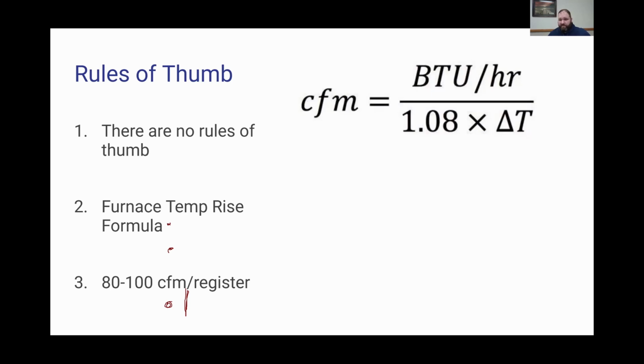You can also look, every furnace has an ID tag from the manufacturer, and it will have a recommended temperature rise on it. Usually, for the brand we sell, the recommended temperature rise range is 35 to 65. So I pick a number in the middle and I design for that. I take the furnace we're looking at, run it through the equation with a recommended temperature rise, and that generates a CFM. I then count the registers with a customer, and that generates a CFM. If those are the same, then we have a pretty good indicator that our furnace is going to match with our duct system.